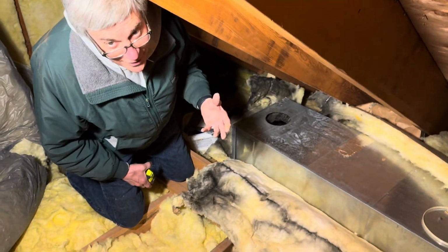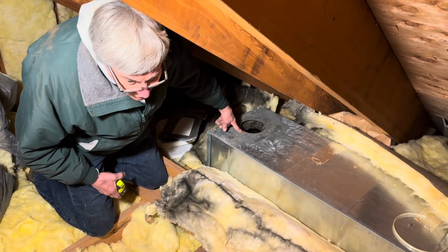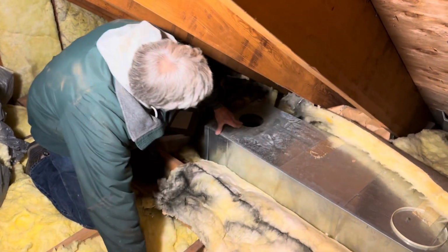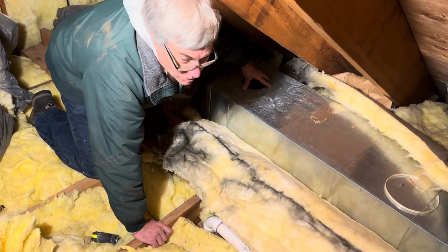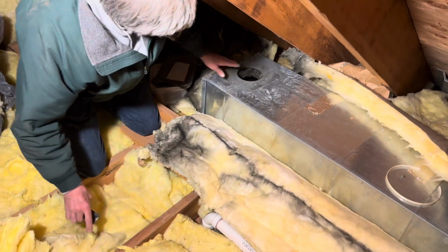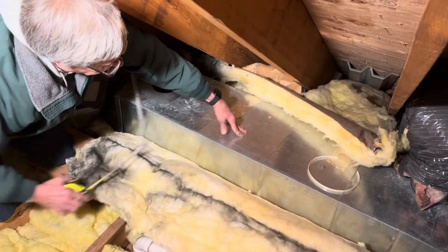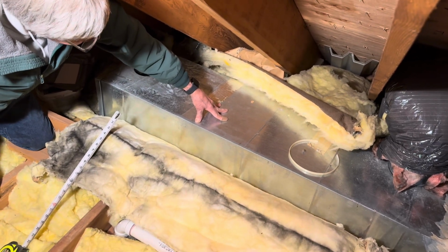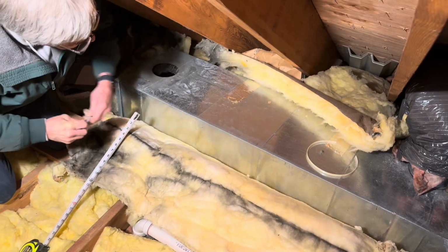So another critical point of design is where we actually put these branch circuits from these takeoffs. Now, if you read the book, which I have read, on proper duct design through ACCA, it tells us we do not want to put any duct takeoffs to start a branch circuit any closer than 2 feet from the very end. So that means we always need 2 feet more of trunk line, which is here. All right, so that's the trunk line that we should have, the last one, before the end of the branch circuit, or the end of the trunk line.